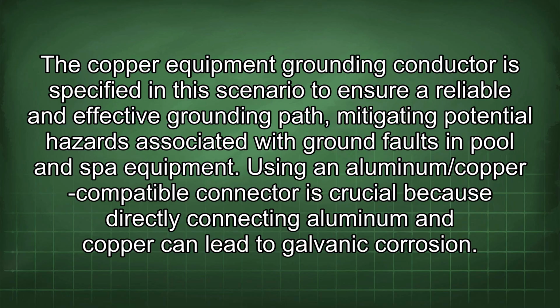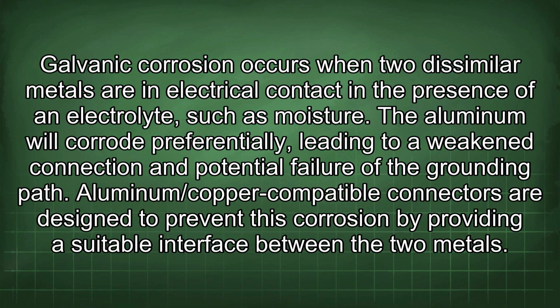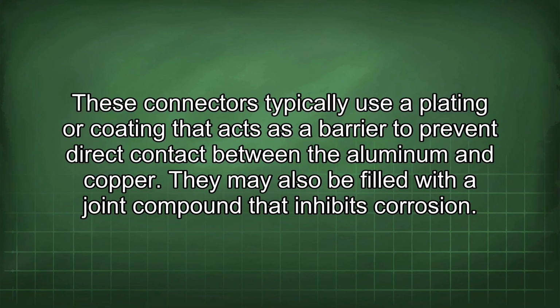Using an aluminum/copper compatible connector is crucial because directly connecting aluminum and copper can lead to galvanic corrosion. Galvanic corrosion occurs when two dissimilar metals are in electrical contact in the presence of an electrolyte such as moisture. The aluminum will corrode preferentially, leading to a weakened connection and potential failure of the grounding path. Aluminum/copper compatible connectors are designed to prevent this corrosion by providing a suitable interface between the two metals. These connectors typically use a plating or coating that acts as a barrier to prevent direct contact between the aluminum and copper. They may also be filled with a joint compound that inhibits corrosion.